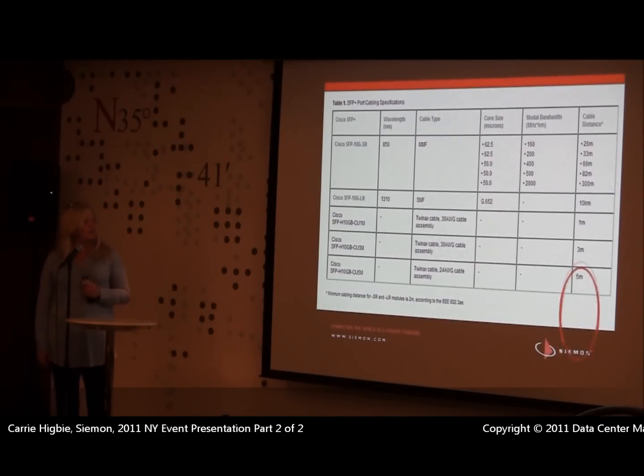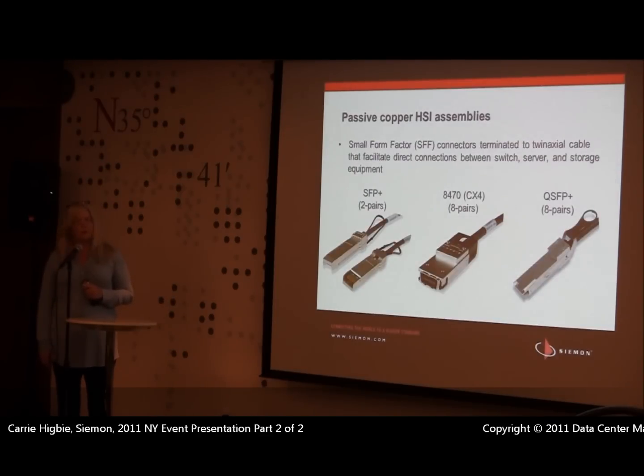If we look at that top of rack technology, though, we are limited to 1, 3, and 5 meters on a twin-ax cable with a switch that's supposed to be in the top of each and every server cabinet. You can do 7 meters actually with active optical, or you'll hear the term middle of row, end of row. But let's look at what it really looks like.